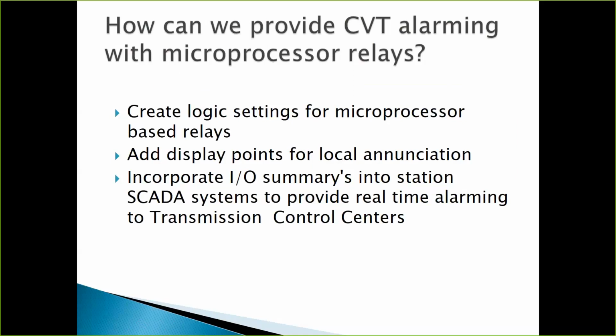You create logic settings for the microprocessor relay. You add display points for your local annunciation at your station, and then you incorporate this setting into your I/O summary, so that through your SCADA system you can notify your transmission control center of the real-time, live status of your devices. So this is kind of a three-step process. And again, it's a higher skill set, but it doesn't take any hardware to do that. Typically, your stuff's already in place.